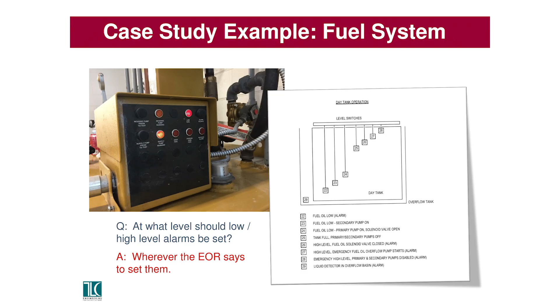Another one I see all the time is a day tank or main fuel tank can have multiple levels of alarms - low fuel pre-alarm, low fuel alarm, and the same on the high side, high fuel pre-alarm and alarm. What level should those be set at? This is a question I get all the time, and my answer is whatever the EOR says they should be set at. And that's a whole different thing.